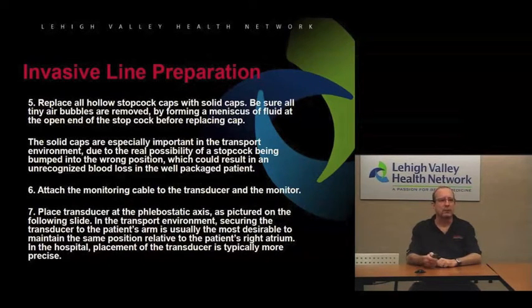And then we attach our monitoring cable from the transducer to the monitor, and then place the transducer at the phlebostatic axis as pictured on the following slide. In the transport environment, securing the transducer to the patient's arm is usually the most desirable to maintain the same position relative to the patient's right atrium.